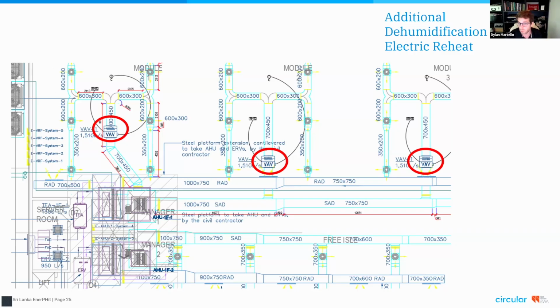Now, let me just quickly explain the concept of reheat, because some of you may be asking, why are we heating anything? We're trying to cool air, right? The reason is that in order to get moisture and water vapor out of the air, you not only have to cool the air down, you actually cool it to an even lower temperature than it will ultimately end up at. As an example, I'm going to use Fahrenheit because those numbers are more familiar to me: you may have 80-degree Fahrenheit air that gets cooled, and you want that air to be 70 degrees Fahrenheit. You're actually cooling that air down to about 50 or 55 degrees Fahrenheit.